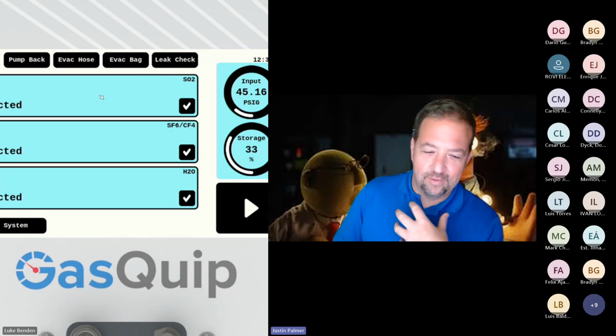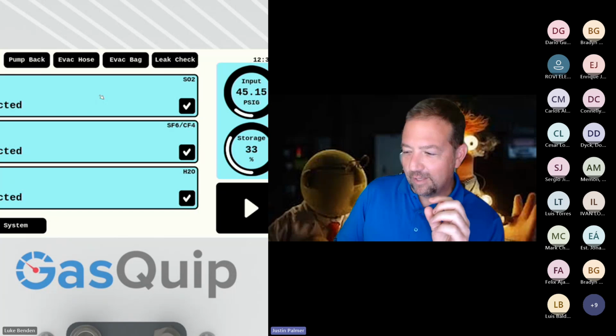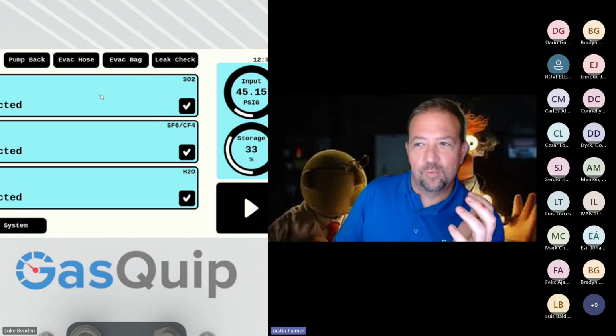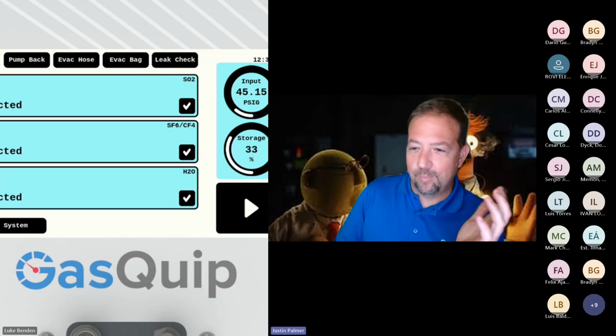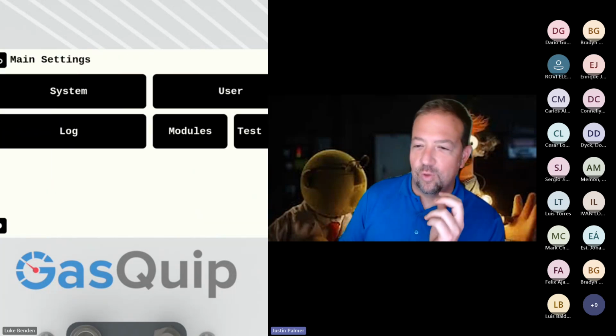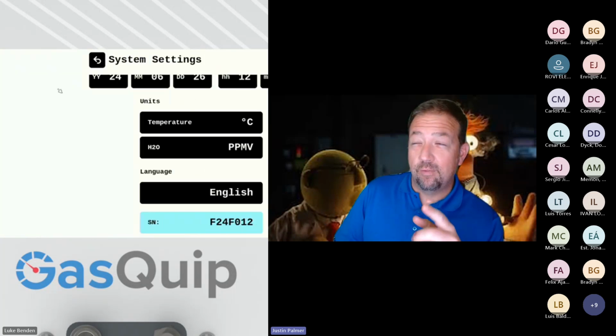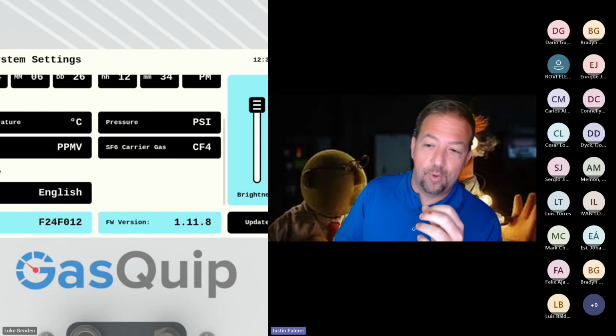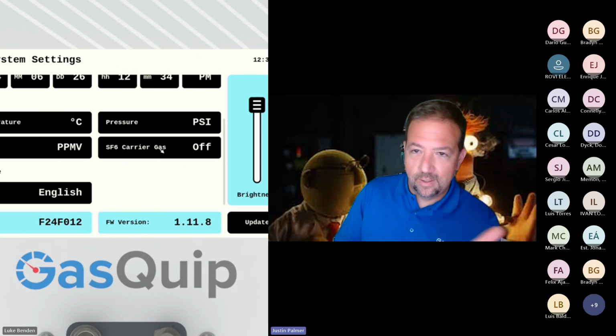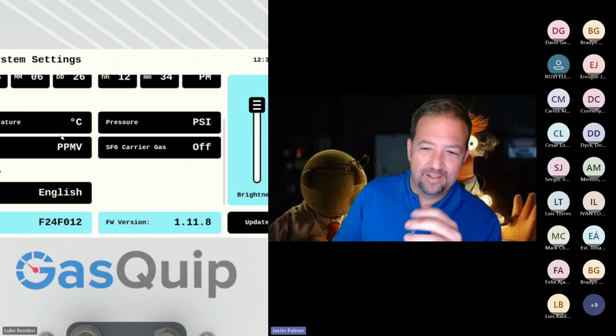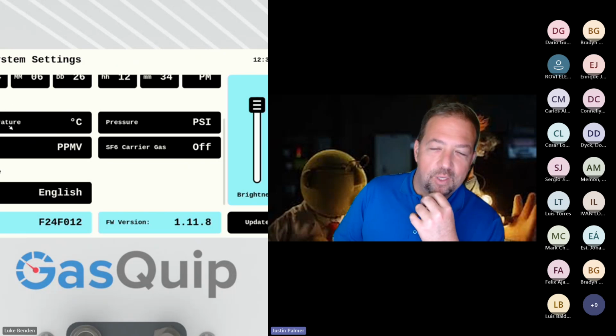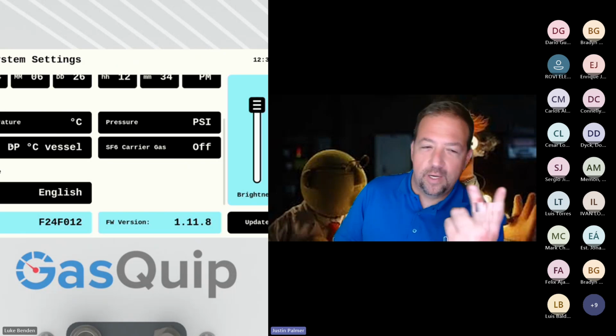It's like I said, and this is my humble opinion, and I've had this discussion with a lot of other utilities, and it's a pretty large amount of us feel it's an absolute waste of time. But to answer the question, you can test down to about 5 psi to get a valid reading. Sometimes you may have to run multiple tests because you have a very, very low gas flow for that, and it's hard to dry the sensors out and get flow through them. So again, not really something I'd suggest. Brad, yes, we can do parts per million by volume and parts per million by weight. You can do dew point at pressure, dew point at atmosphere, and I think Celsius and Fahrenheit, depending on what you like.